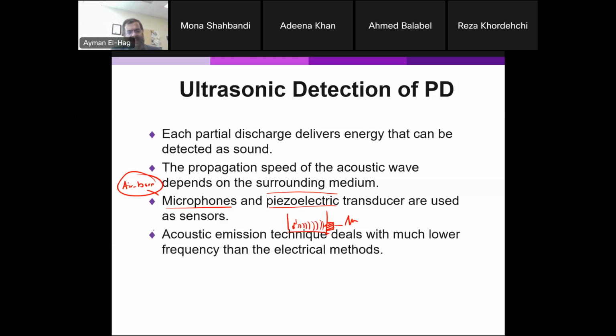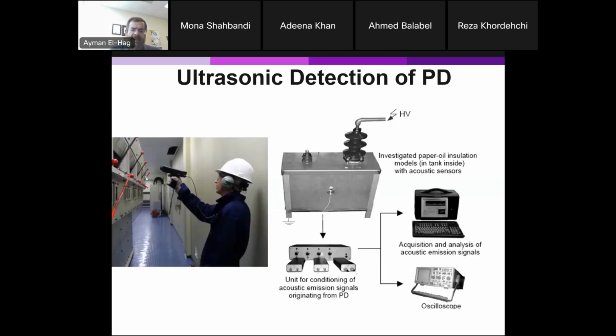Now, an advantage here is that the range of frequencies is much smaller than the electrical methods. And because of this, the data acquisition system doesn't have to be expensive, because instead of gigahertz or hundreds of megahertz, I'm dealing with kilohertz. So the acquisition system becomes extremely less expensive compared to the RF.